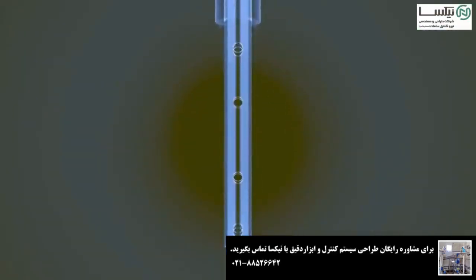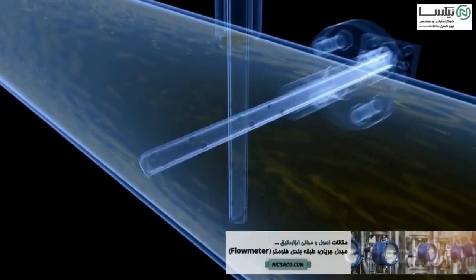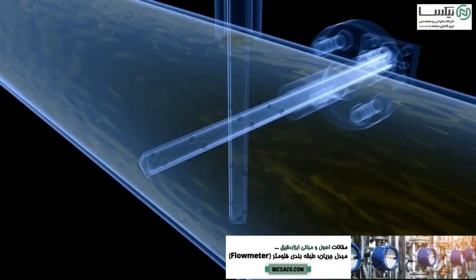The individual pressure taps are distributed along the entire pipe cross-section to ensure a representative measurement. If there is strong interference in the flow profiles, it's advisable to fit a second Pitot tube, rotated by 90 degrees.